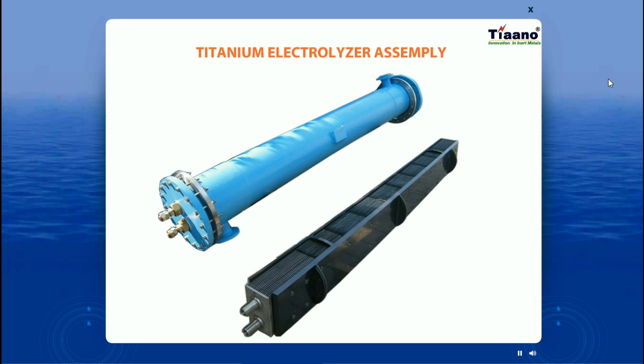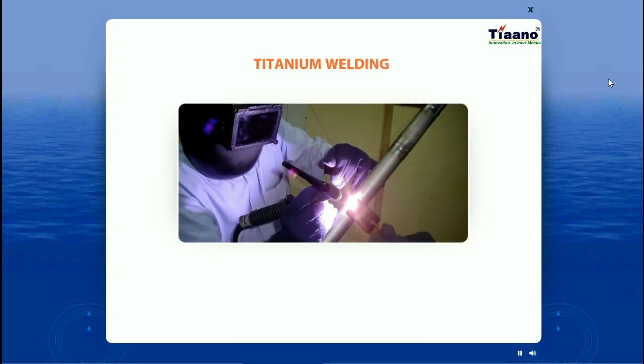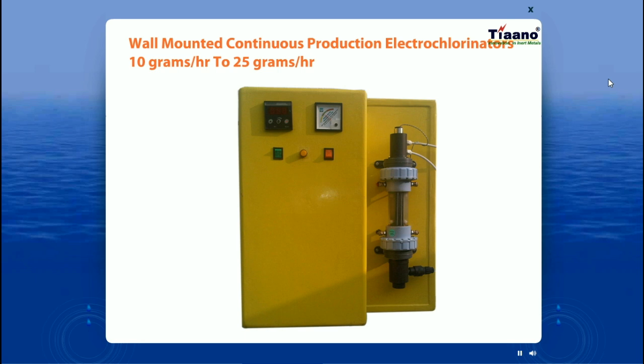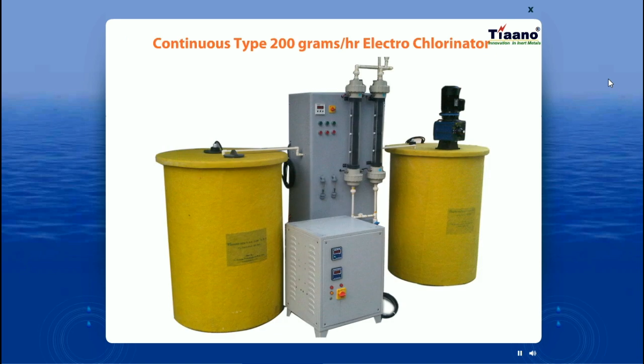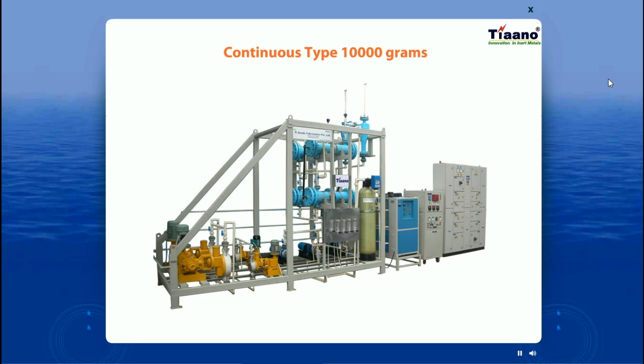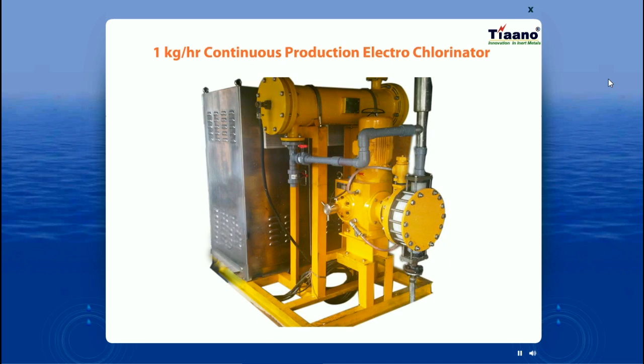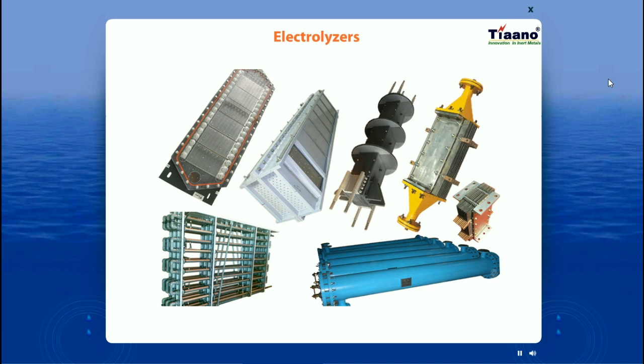The electrolyzer is made of titanium and coated with mixed metal oxides of platinum, welded using a special process. Continuous production models range from low-capacity wall-mounted types to medium-range compact fully automatic units, and high-capacity systems starting from 500 grams per hour up to 500 kilograms per hour, operating on brine solution or seawater. Very high-capacity systems are supplied with pumps, brine dilution systems, storage tanks, hydrogen venting systems, PLC control panels, hypo dosing pumps, and acid cleaning systems.